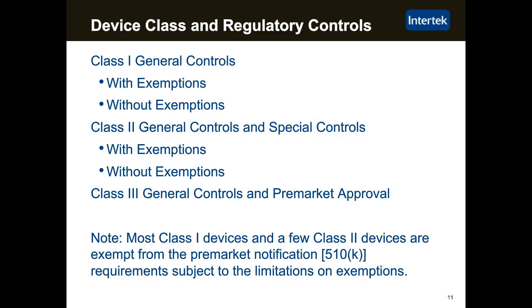And then in the case of Class 3 devices, general controls apply, but also the requirement for a pre-market approval. So as a note, most Class 1 devices and a few Class 2 devices are exempt from pre-market notification, which we call the 510K process. But those requirements, where there are exemptions, are subject to certain limitations. And that information is typically found once you identify a class of device on the FDA database. It will tell you whether or not that device is exempt from 510K pre-market notification or if it is exempt from good manufacturing practices.